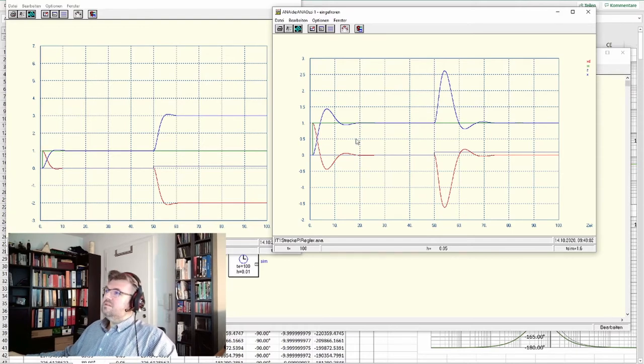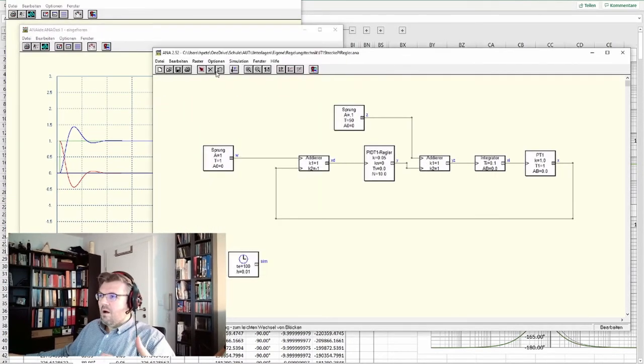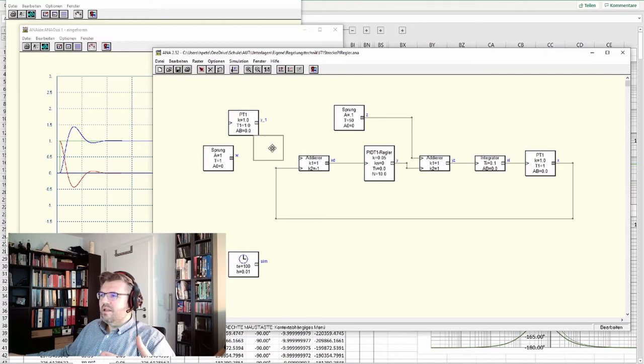What we can do about this is simply add a pre-filter. We do not have to use the jump here. I will kill this one and simply enter a PT1 element as a filter element here. So this is the reference value, and I will not use the reference value as a jump.